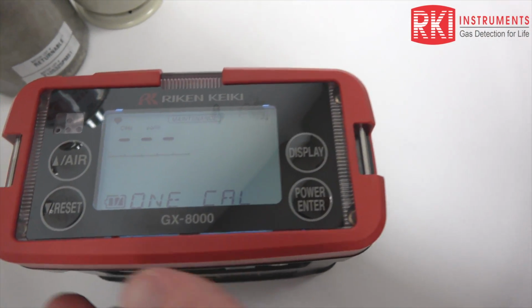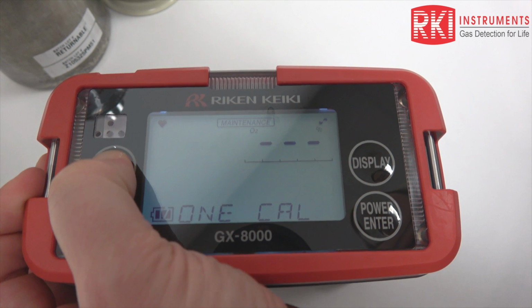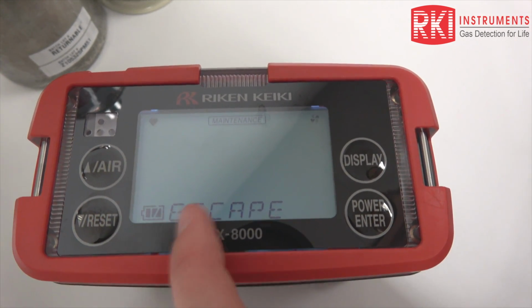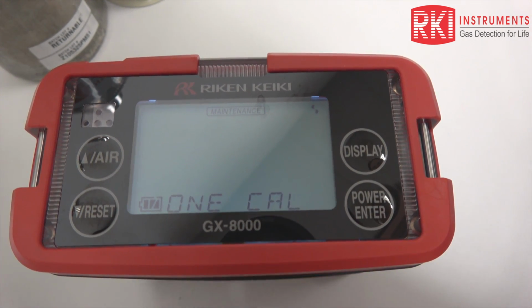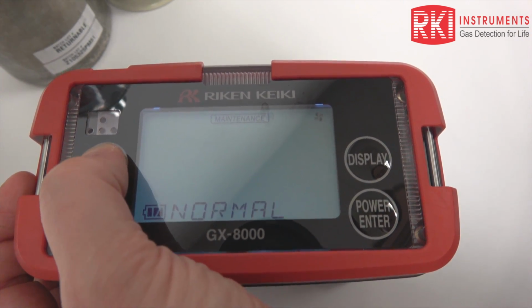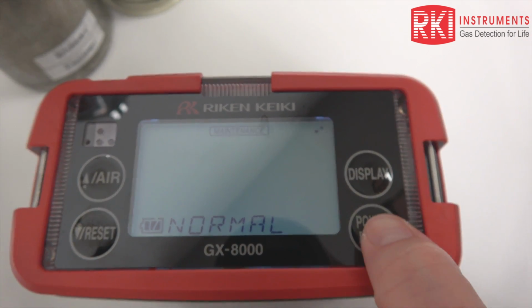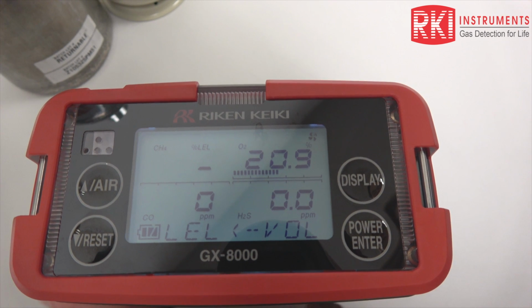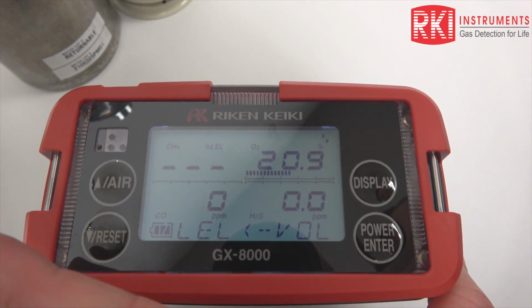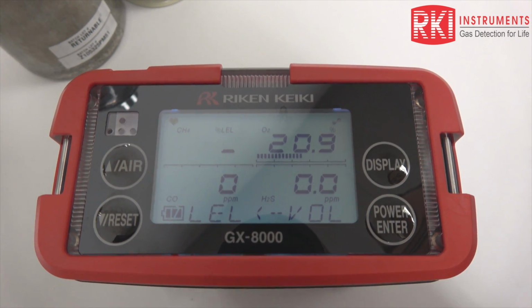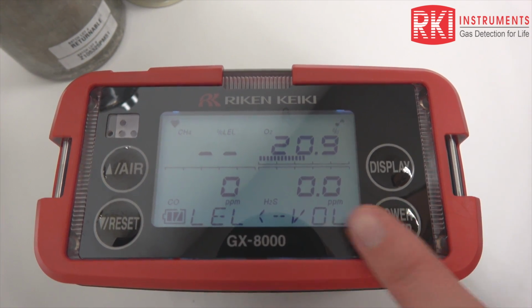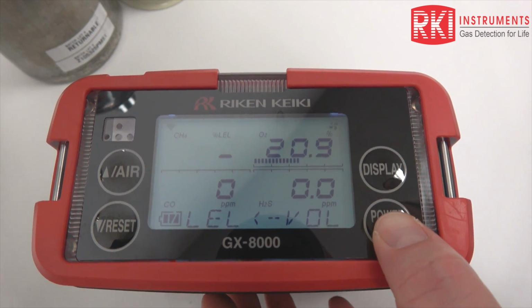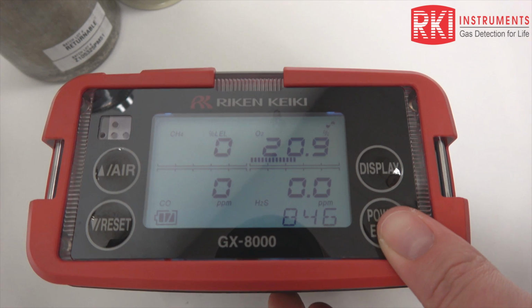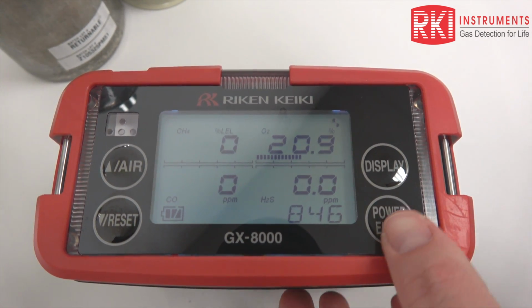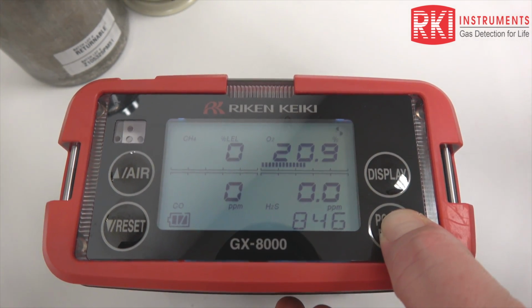Okay, so now I'm done calibrating all of my sensors. So now I want to back out of this calibration mode. So I'm going to scroll until it says escape. Let's say power enter. Now we're going to scroll till it says normal. And now we're back here at the normal screen. The LEL is still warming up because we just applied that very high percent volume gas to it. So I'm going to turn the instrument off now, even though it's not fully back to normal. Oh, here we go. Now it's back to normal. I'm going to turn the instrument off so we can replace the sensors.